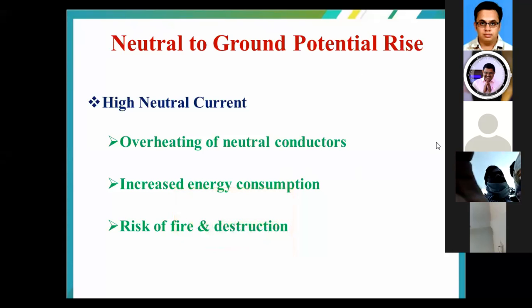And in larger establishments like data centers or textile manufacturing units, we are often facing fire hazards or fire accidents because of this problem, that is the high neutral current or the neutral to earth potential rise. And because of this, the companies or manufacturing units suffer losses in terms of crores, a huge quantum.